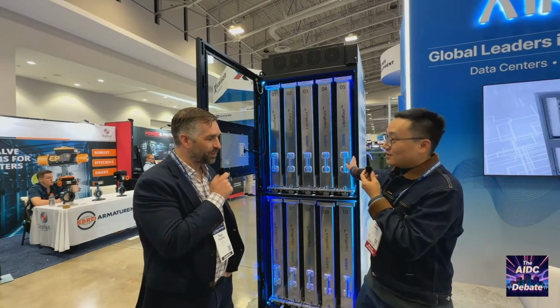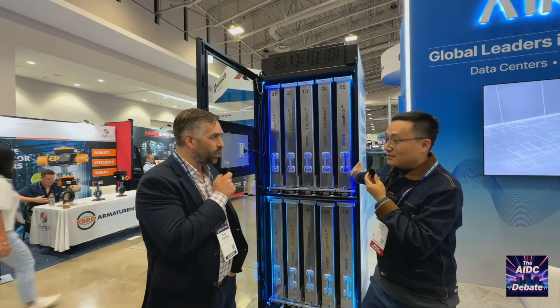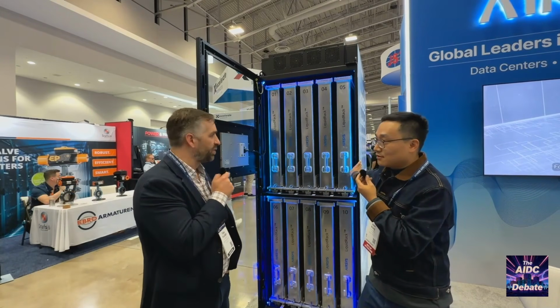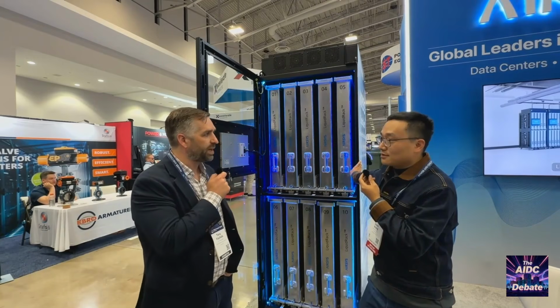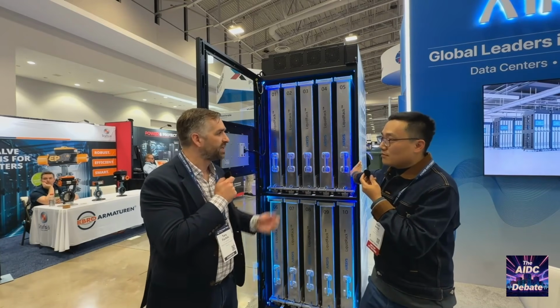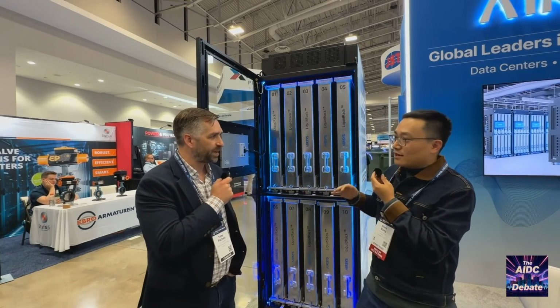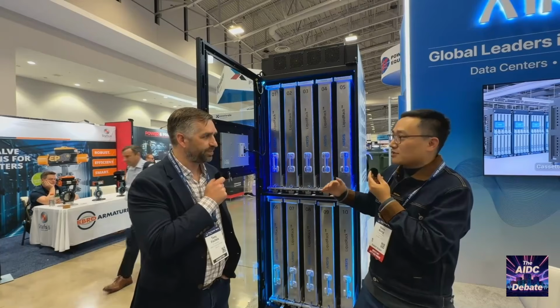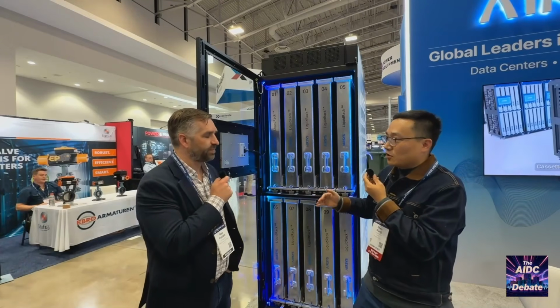What is the maximum capacity of this rack? With a dry cooler and higher temps, around 80 kilowatts for the rack, 8 kilowatts per cassette. So we're looking at high density CPUs rather than high density GPUs - I think that's quite enough for not-so-hyperscale AI deployments.